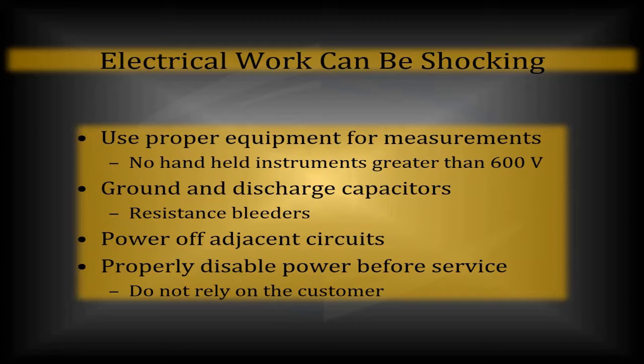Power off any adjacent circuits. Why would that even matter if you're powering off circuits nearby? Well, there's something called induction. If you've got power wires running next to each other, even though they're not connected, there's a magnetic field around them. We know that field is there because we use those little pen lights to detect whether voltage is present. You take the little pocket meter out, put it next to a wire, and it lights up, maybe even makes a beep noise. What's actually happening is inside that pen light there's a circuit powered by a battery, but at the very end you have contacts.